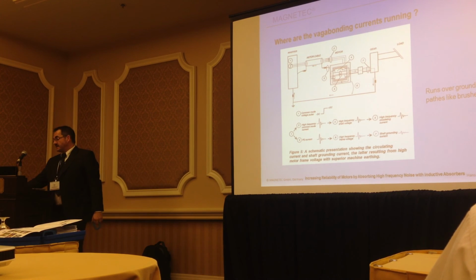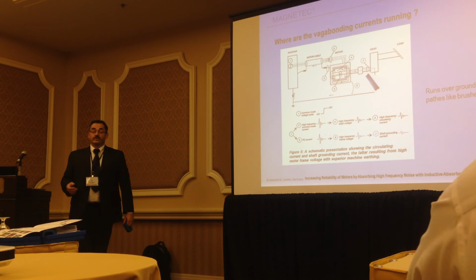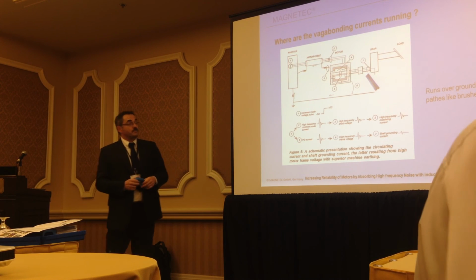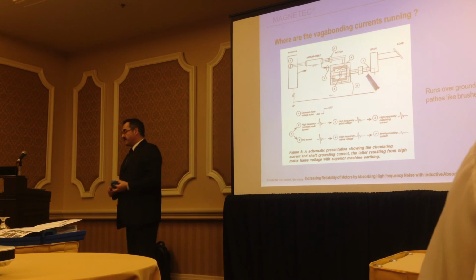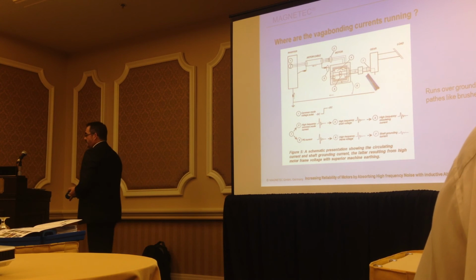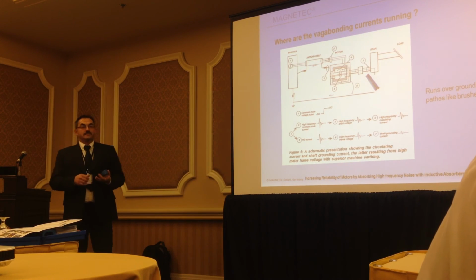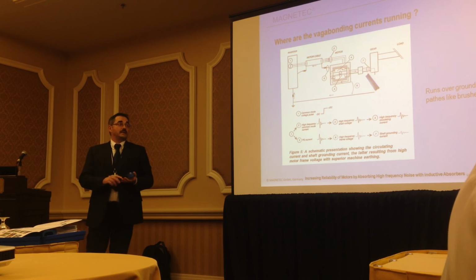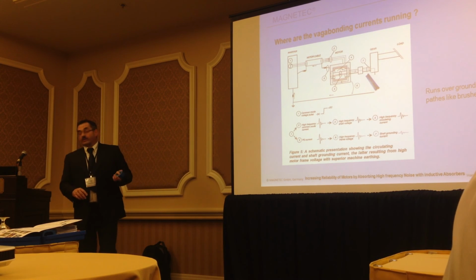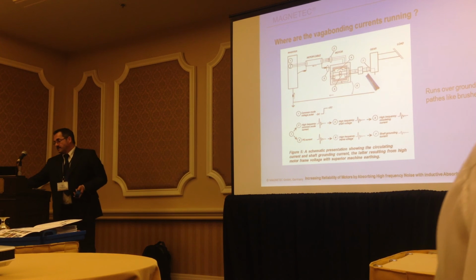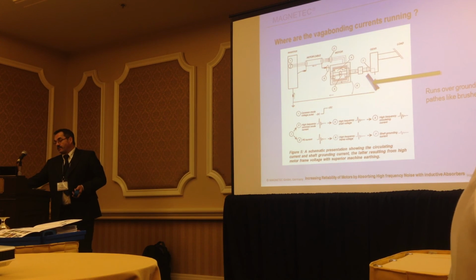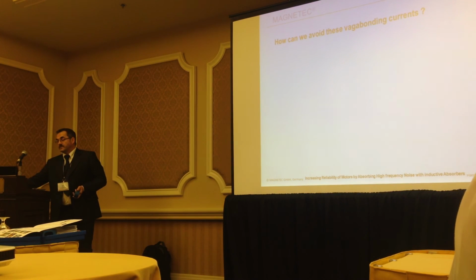You can describe the path of this, but a typical way to avoid or reduce it was using a shaft grounding brush. The brushes have the good thing that they immediately reduce the voltages. The problem is dirt, the mounting is not easy, and it's all very costly. So the target now is to avoid brushes and use another solution.